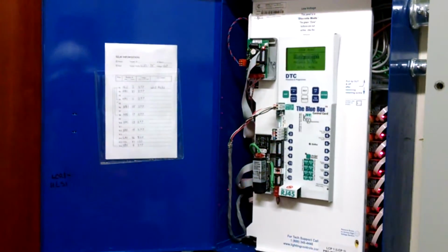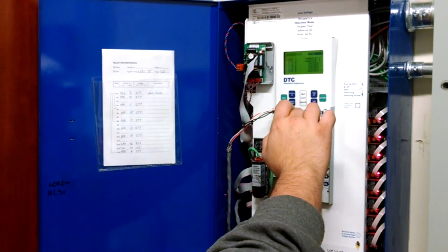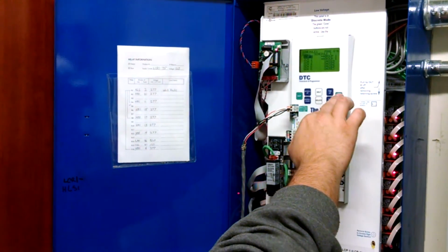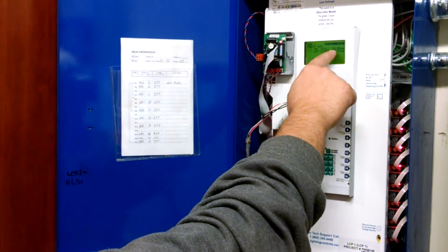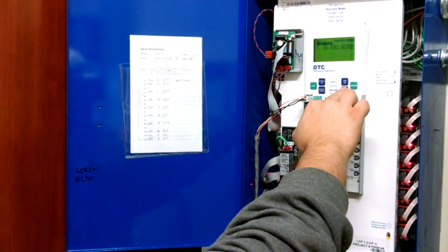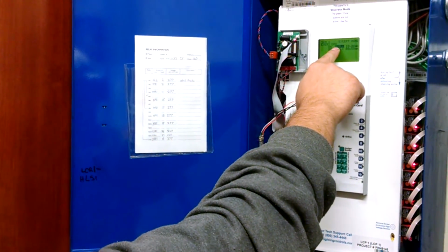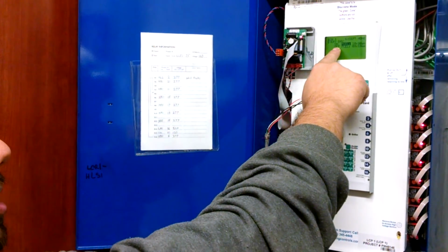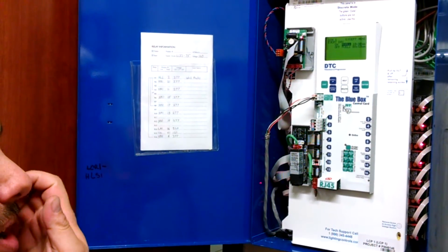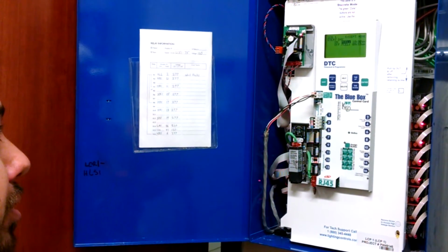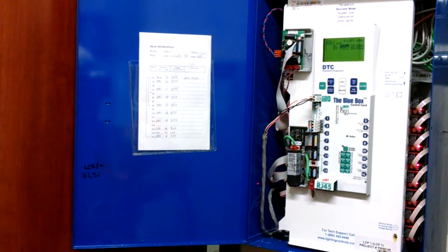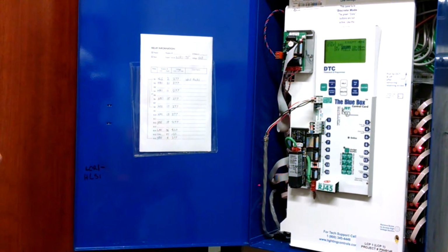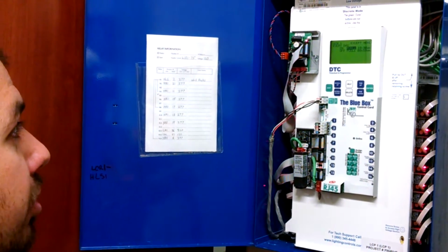Review schedule. This is where the actual schedule lives. If we come down into schedule number 1, we can see that the photocell is controlling our lights. What we're doing is basically enabling the photocell from 10 a.m. till 9:59 a.m. the next day. So there's 1 minute a day where the photocell doesn't work, between 9:59 and 10 a.m., and the rest of the day it actually does control the lights.